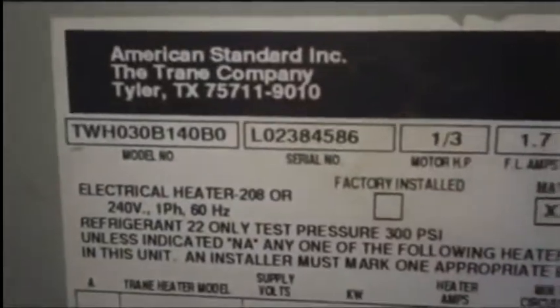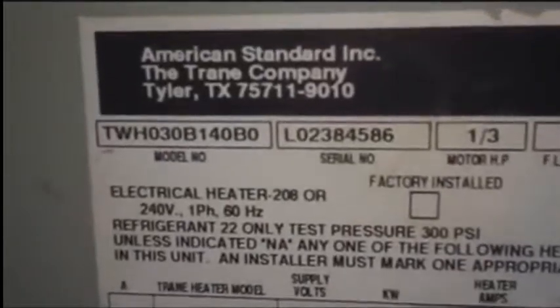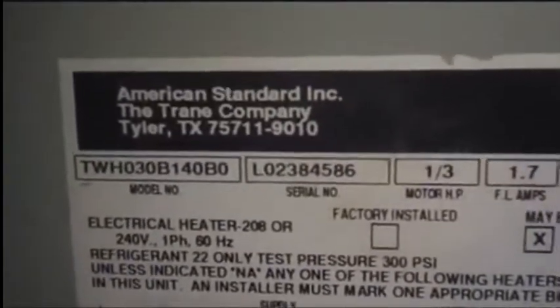This is the air handler we're changing out, and I'm up here at the air handler door to check the indoor coil to see if it's frozen over, because it's been freezing all day and getting worse. I want to see if the coil is totally blocked up with ice and needs to thaw out. It's a good time to change the unit, but I want it to last a few more days so we can finish the whole install and get it going.